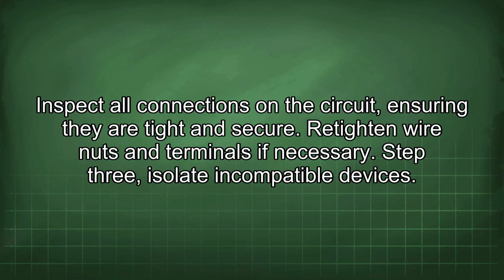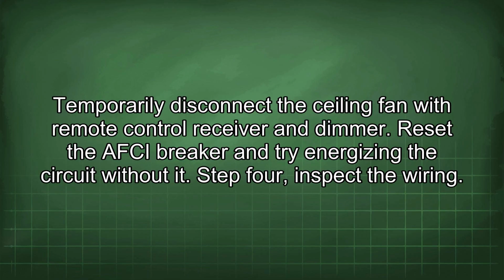Step 3. Isolate incompatible devices. Temporarily disconnect the ceiling fan with remote control receiver and dimmer. Reset the AFCI breaker and try energizing the circuit without it.